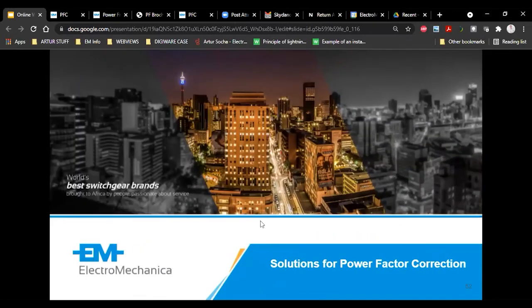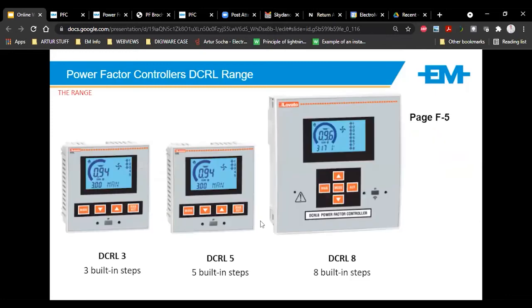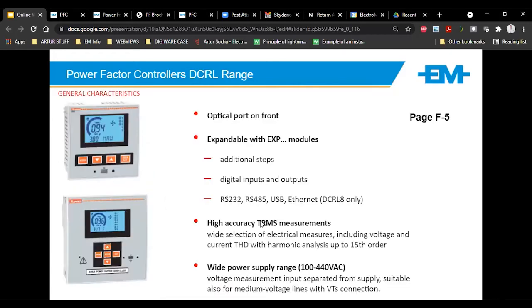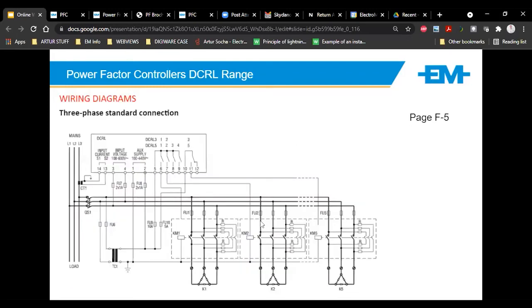Okay. So that's the brief on just power factor and a bit of harmonics. Solutions from EM for power factor correction. We've got a full range of controllers. Some are more basic. This is the DCRL range. Depending on how many steps you would need or how many banks, this could be an option. These are typically used for our smaller systems, our wall mount systems. It only needs one CT and it works on two phases, measuring on 2 phases, but it would bring in a 3-phase capacitor. All right.